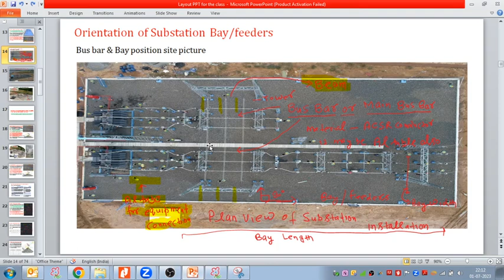The conductor is, according to me sir, for about 33 kV system, until we can go to 66, we should use the aluminum IPS rigid busbar system, and for greater than 33 or 66 kV, we can go for the flexible ACSR, because ACSR is flexible and costly, so the cost is justified for high voltage.